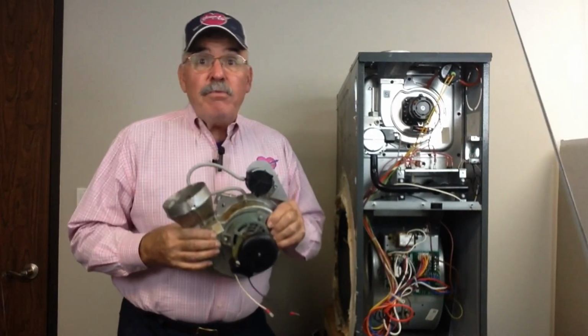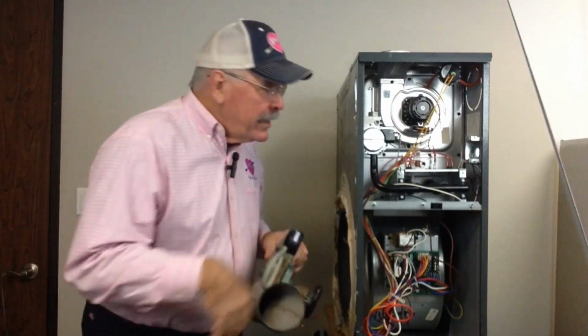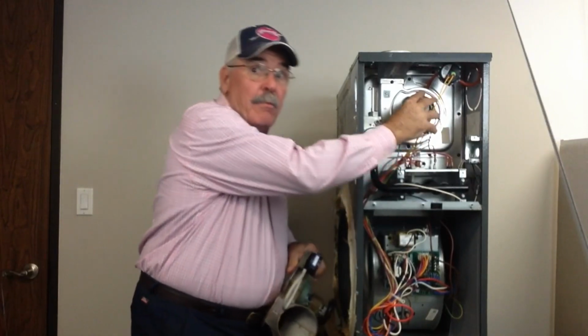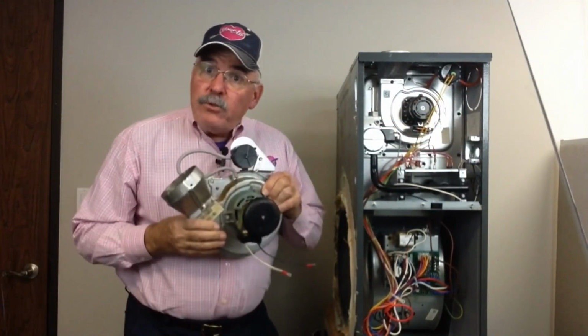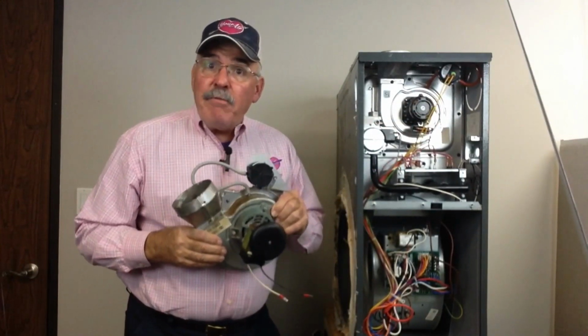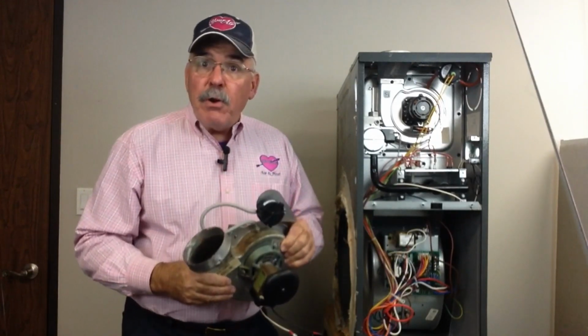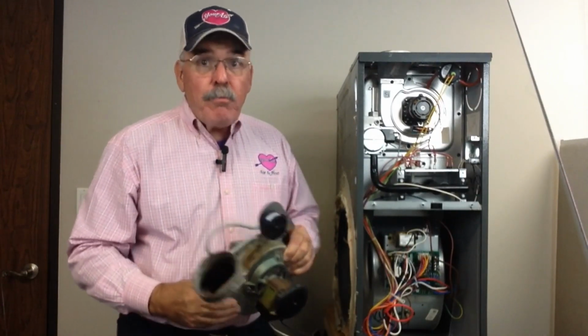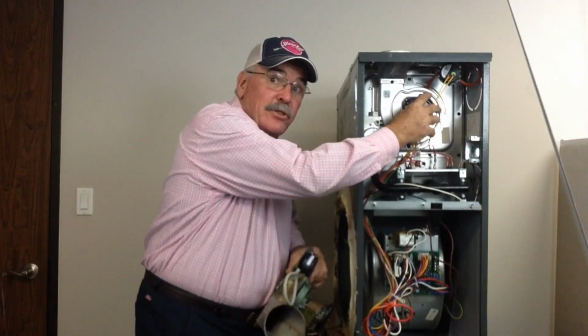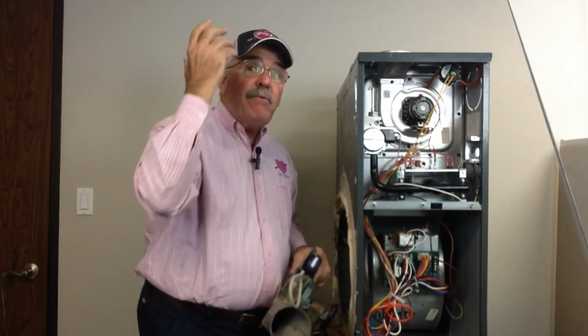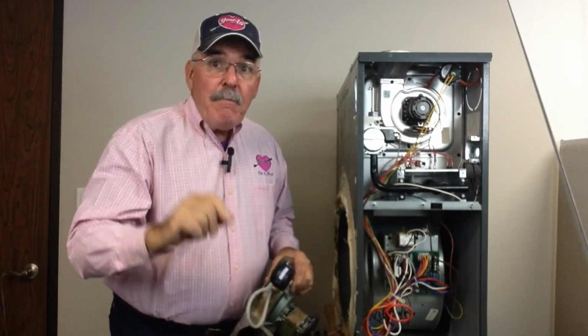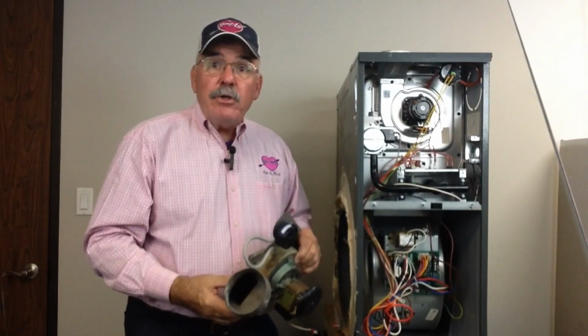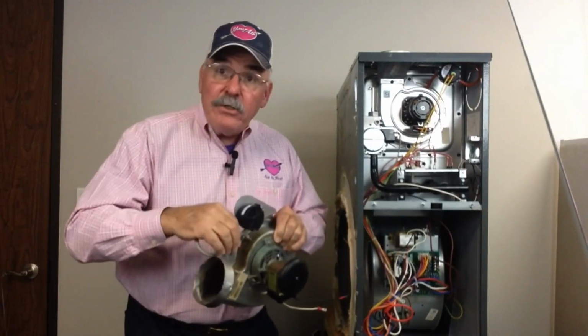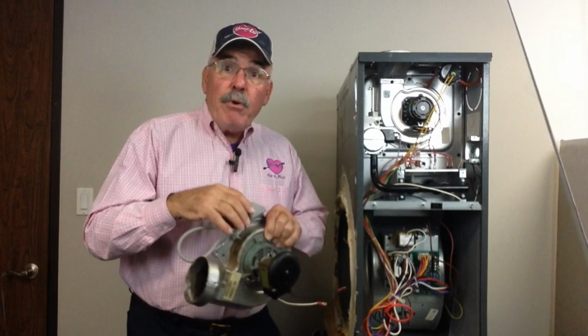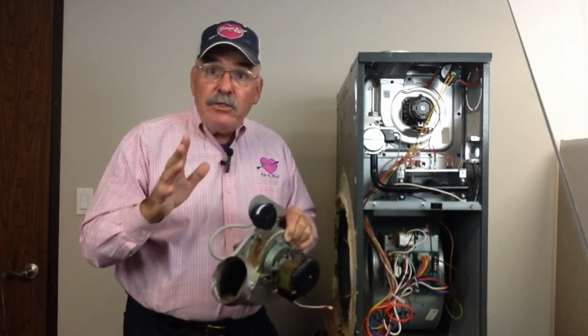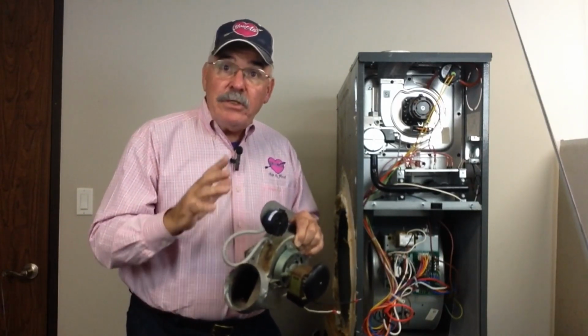Now this inducer fan assembly is attached to your heat exchanger right here. And when it's working, its job is to create a vacuum pressure so all the unburned gases and carbon monoxide are pulled from inside of that heat exchanger and then pushed out of the flue pipe so you're safe. Now the inducer fan assembly also has 1 or 2 vacuum ports on it, just like this, that go to your pressure switch right here, which is the next device in the series of safeties in the system.